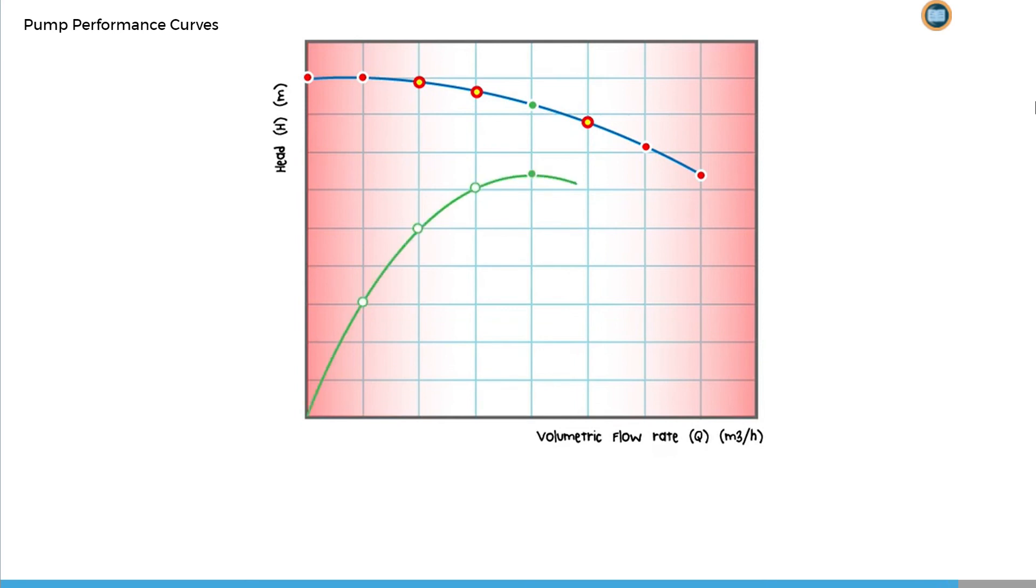There will be a point where the pump is developing flow and head at maximum efficiency. This is called the duty point, and this is the point at which the design discharge head and flow rate meet on the pump performance curve.